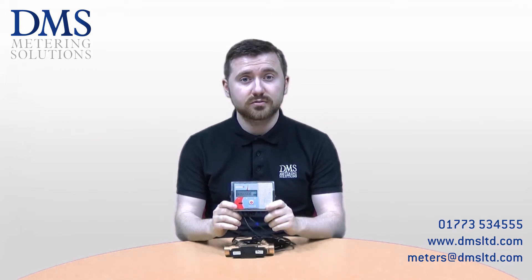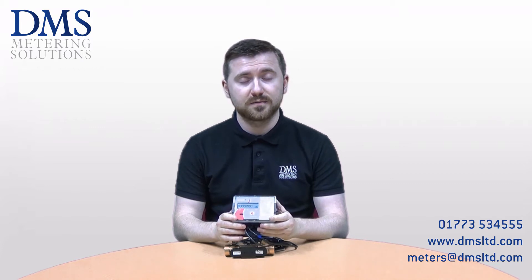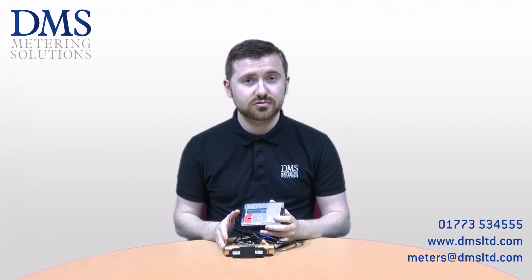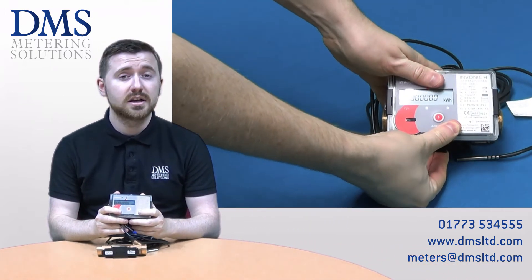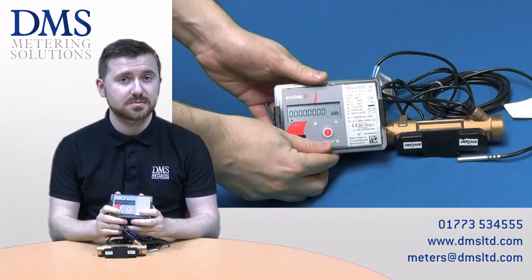The InVONE range are ultrasonic heat meters available in connection sizes from 15mm up to 50mm. These meters can either be supplied with a BSP screwed connection or with a PN16 flanged connection as an option. At 50mm it is just a flanged model that is available, not the BSP screwed.